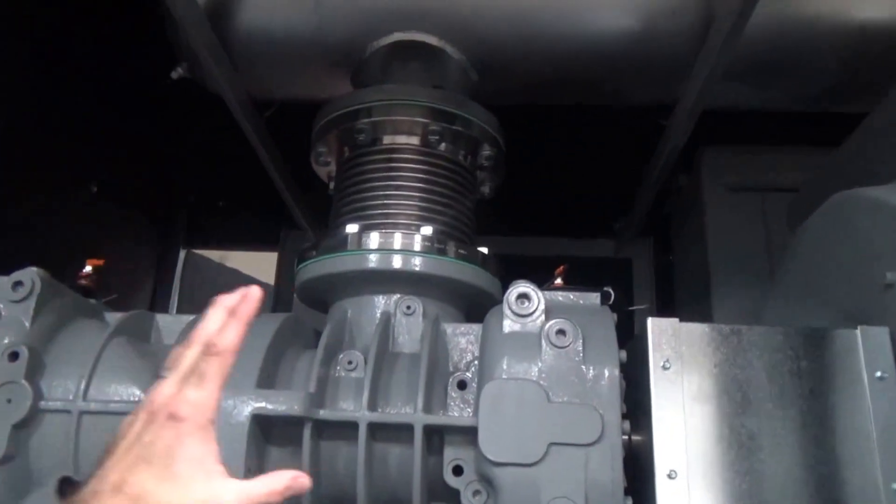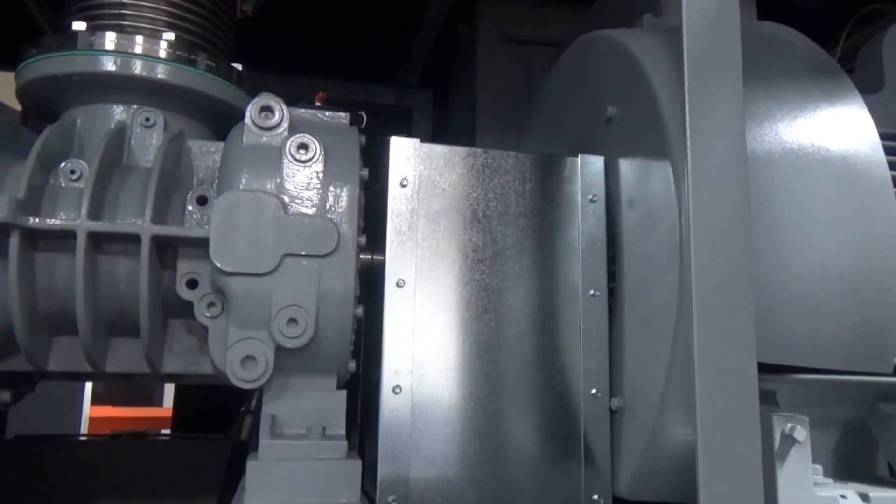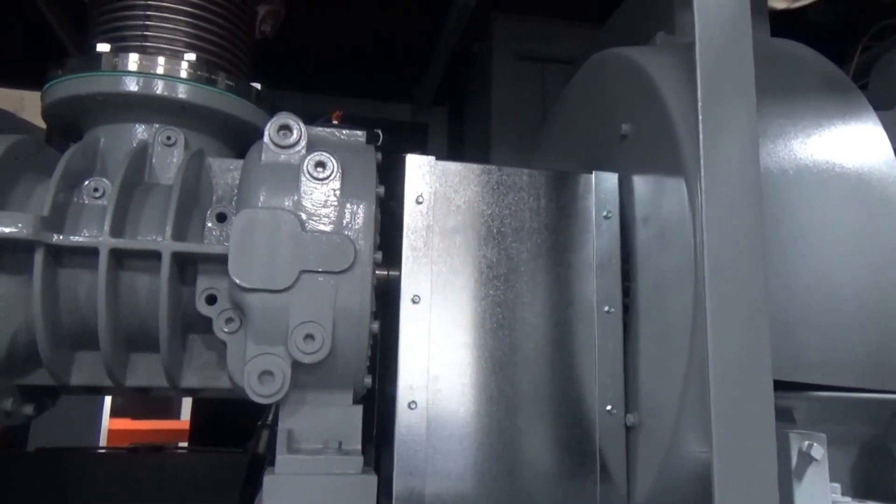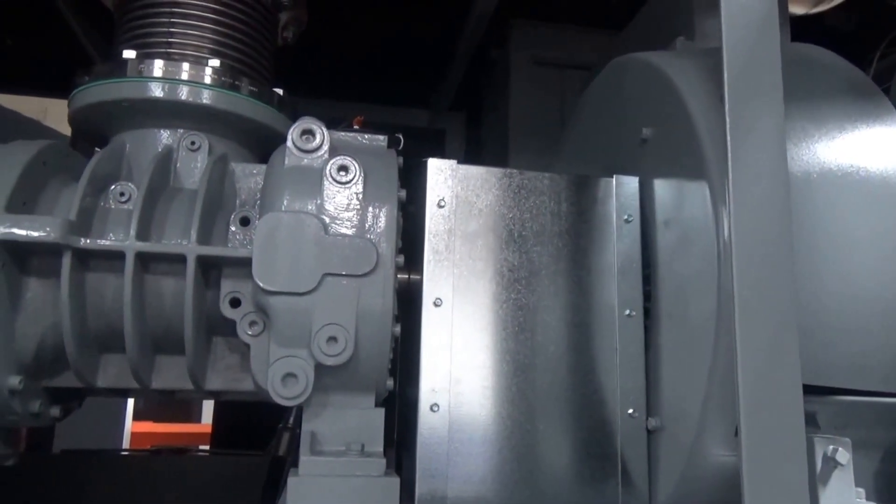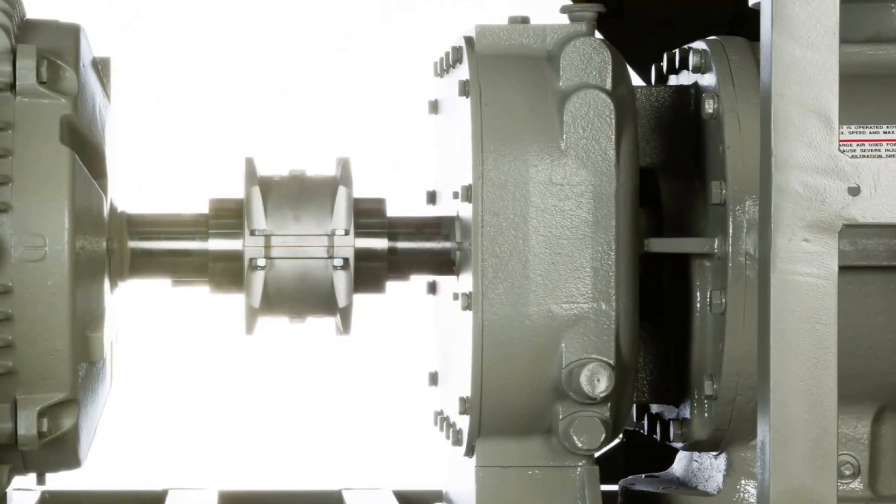The blower is coupled directly with a Baldor 350 horsepower, 4160 volt motor. Direct drive coupling eliminates any belt losses. It allows you to put the blower on a VFD, ramp it up, ramp it down to whatever your process needs.